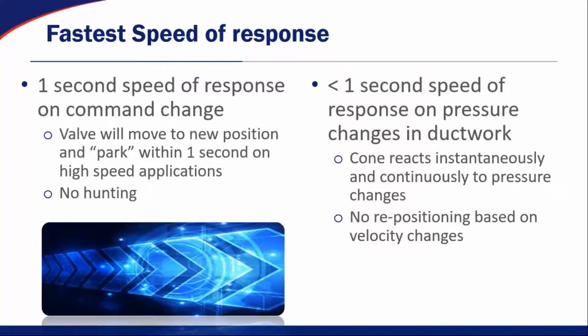What that means is when I move my fume hood sash, my valve is tracking as fast as that sash is moving. And by the time I stop moving my sash, within 1 second, not only is my hood valve going to position to its final position without hunting, but my general exhaust and my supply valves inside that same pressurized zone are also going to achieve their set point and park without hunting at all.